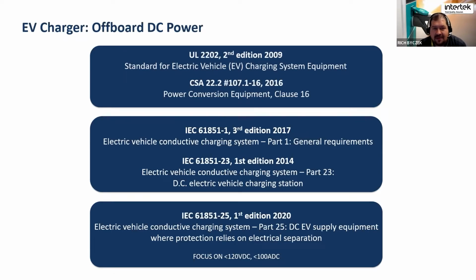Again, the protocol is not defined in the safety standards, but they do have to demonstrate the same functionality can be implemented. Here in North America we have UL 2202, essentially the legacy standard for all EV charging. If you don't have a system that falls under another existing standard, generally UL 2202, or CSA 107.1 for Canada, would be the standard you'd look to for understanding the exact protocol to evaluate the key functions, regardless of it being AC or DC. But because there is now an AC standard for those countries, 2202 has been relegated to DC charging and other unique applications. Within IEC we have the 61851 series, specifically -23 for the DC electric charging station.